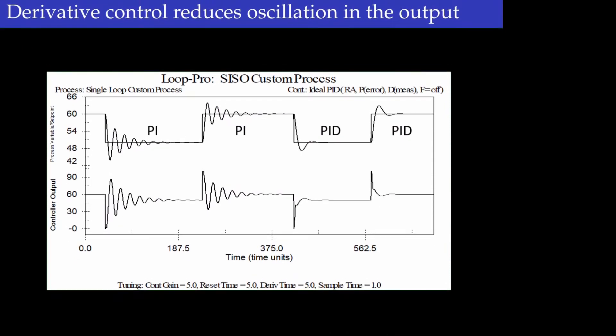Looking at the response of a process under PI control versus PID control, under PI control the output was oscillating significantly. For the same proportional-integral parameters, when you use the PID controller — meaning adding the derivative part — the oscillation reduces to a great extent, and the variability in the input also changes significantly.